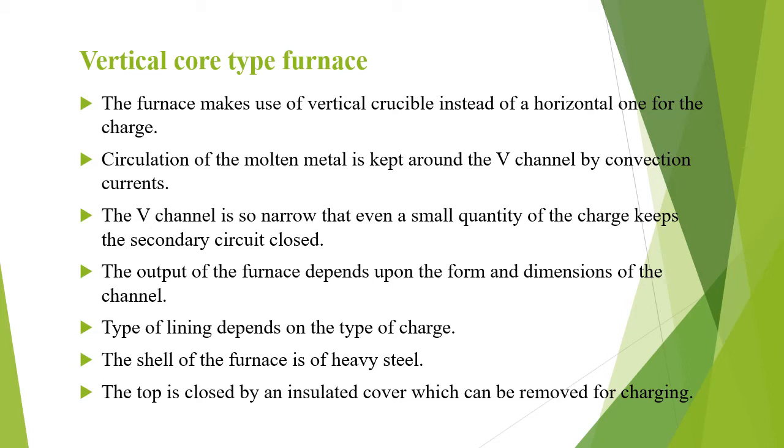The power factor of this furnace is comparatively high. The output of the furnace depends upon the form and dimension of the channel. Apart from the V-shaped channel, we can have U-shaped and rectangular channels employed. The type of lining depends upon the type of charge. The shell of the furnace is made of heavy steel, and we have the top closed by the insulator cover, which can be removed for charging purposes. Also, tilting of the furnace to pour out the metal is done by hydraulic means.